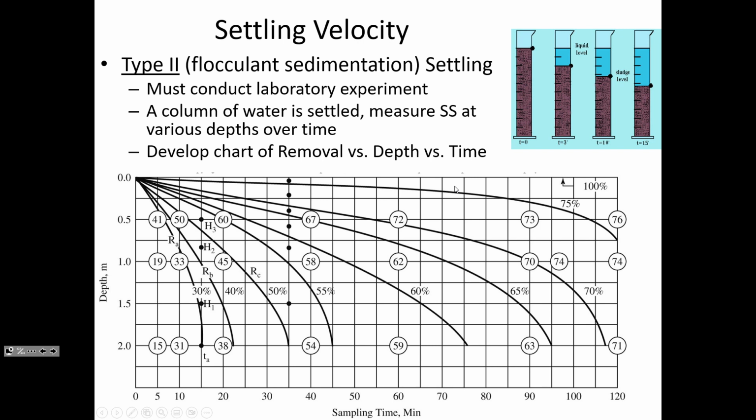And a typical rule of thumb is if you do this lab test and you're kind of designing your process around a worst case scenario, so you don't assume that the coagulation flocculation process is perfect. You assume maybe you have your highest turbidity input water and kind of compromised performance with coagulation flocculation. So it's kind of just like a marginal level of settling that you think that you can achieve most of the time is how you design your settling basin for.